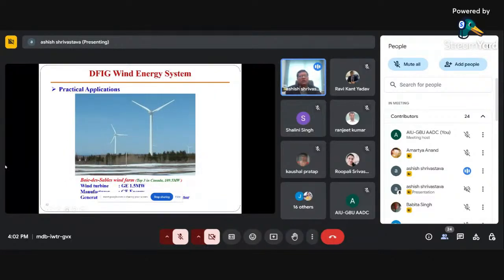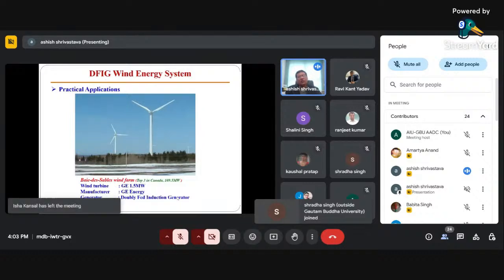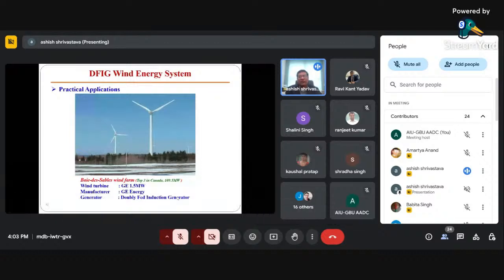Now, this is a practical application. This is a 1.5 megawatt wind turbine, and the manufacturer was GE Energy, and it is with a DFIG, doubly fed induction generator. So now I will be discussing the next one, the DFIG, doubly fed, because here from the stator power is fed to the grid, and then from the grid the power is injected back to the rotor, at slip frequency, because at the rotor the voltage is of slip frequency. So now it is not a full converter, it would be at reduced power. So I will be showing you that.